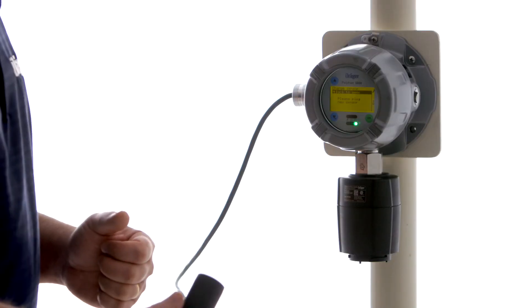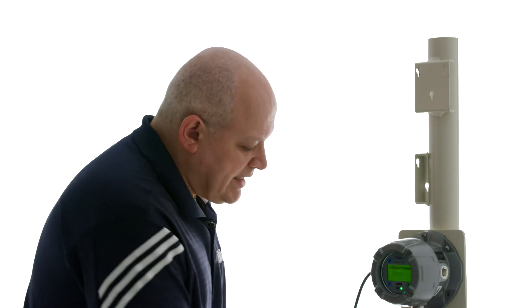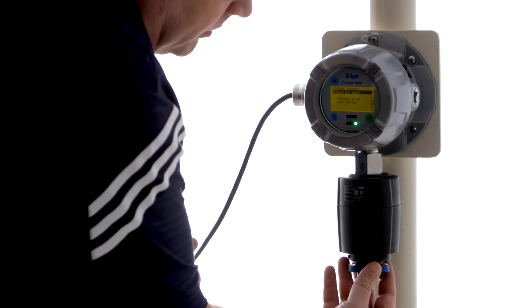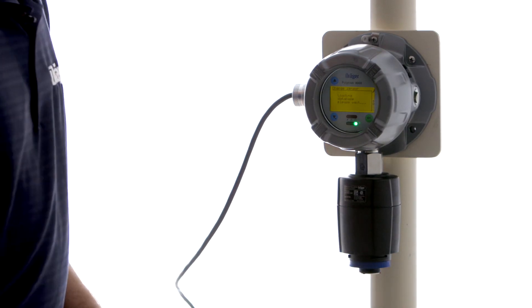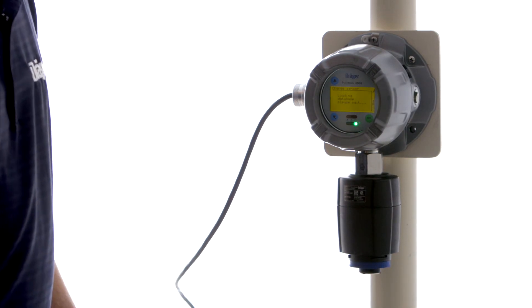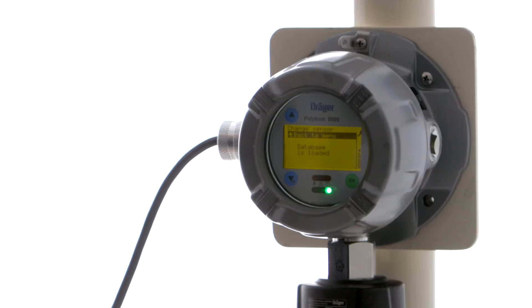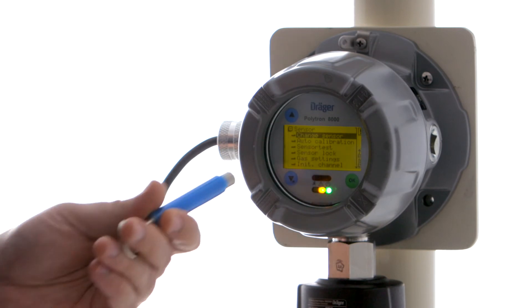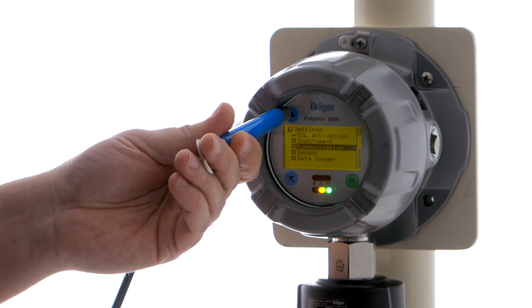So now we're going to put in a new sensor. As long as we're putting in the same sensor with the same part number, it will retain the configuration. The Polytron 8200 will not change any other configuration. So now we'll put in a new CO sensor with the same part number. Our database has been loaded and we can go back to the main menu.